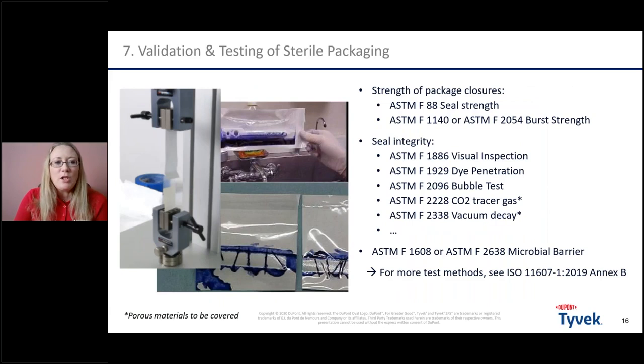In terms of validation and testing, I've listed a few typical test methods used a lot with porous packaging, like Tyvek packaging, but also other packaging types. For strength, you need to demonstrate that your seal strength can withstand handling, sterilization, transport, etc. You can test with ASTM F88, shown on the left with the tensile strength equipment, which is very precise because you can examine and judge all the different seals.